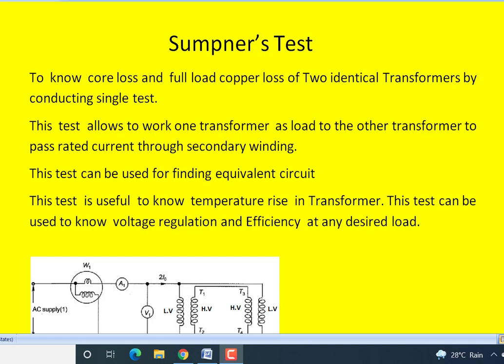And the other thing is, in Sumpner's test, one transformer acts as load to the other transformer to pass the rated current through their secondary windings. And this test can be used for finding the equivalent circuit of each transformer. Also, this test can be used for getting the voltage regulation at any given power factor under any load conditions. Similarly, we can also find the efficiency of the individual transformer at any desired load and power factor.